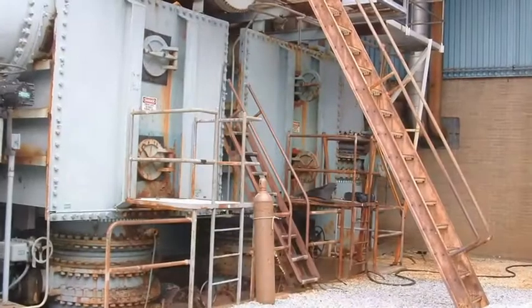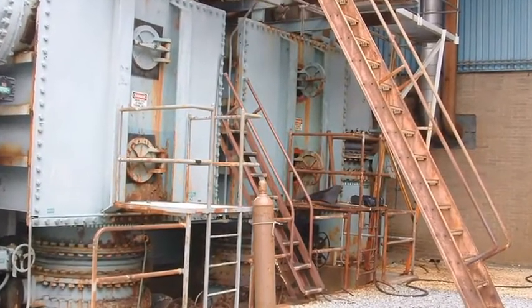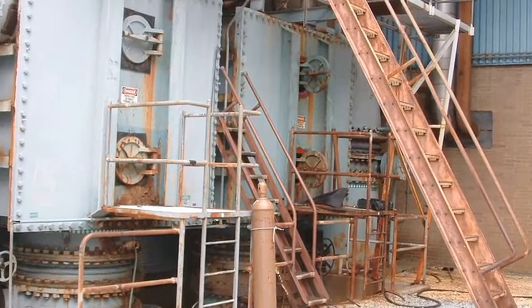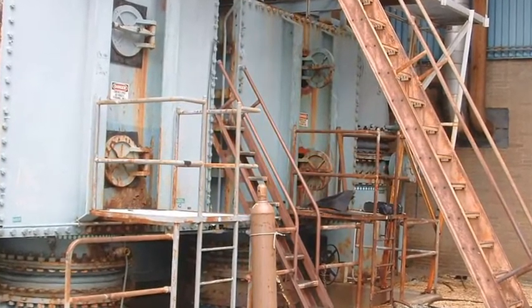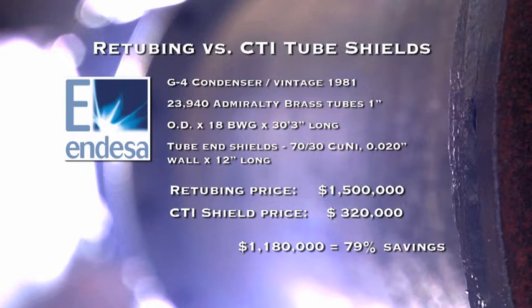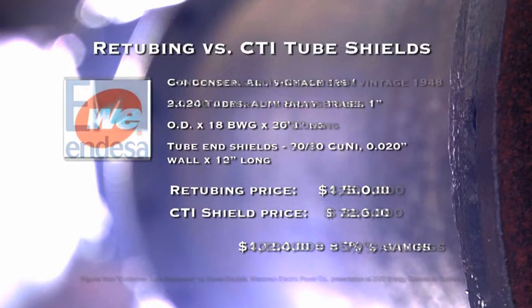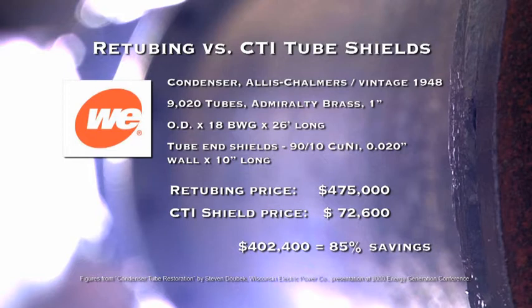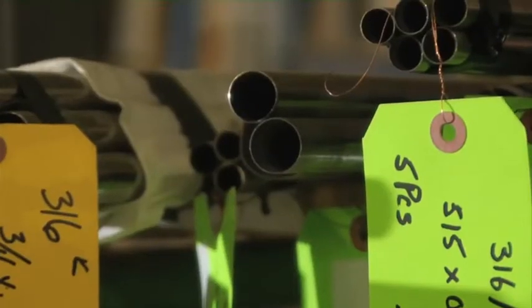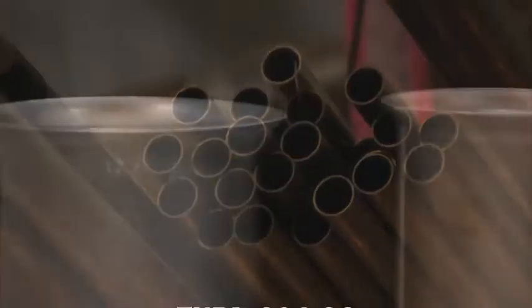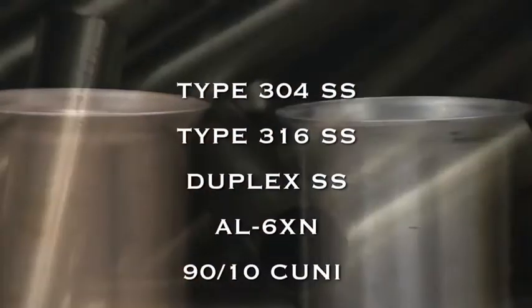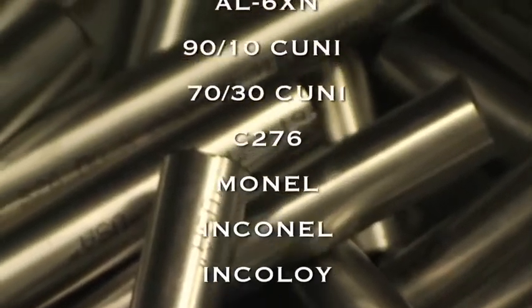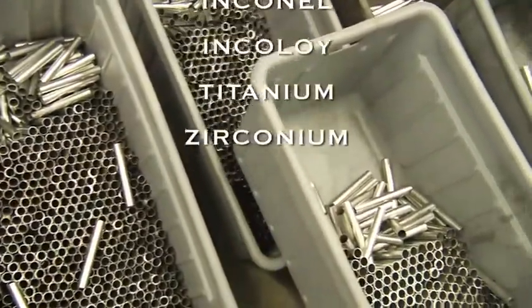For large steam condensers, water boxes remain in place and workers gain access through the manways, eliminating another major task required for retubing. Companies can save up to 90% of the cost of retubing and provide years of equipment life extension. Material selection is critical, and CTI is able to provide sleeves in many different alloys. The choice is typically a superior but compatible alloy to that of the original tubes. This will increase the erosion corrosion resistance, yet maintain galvanic compatibility.